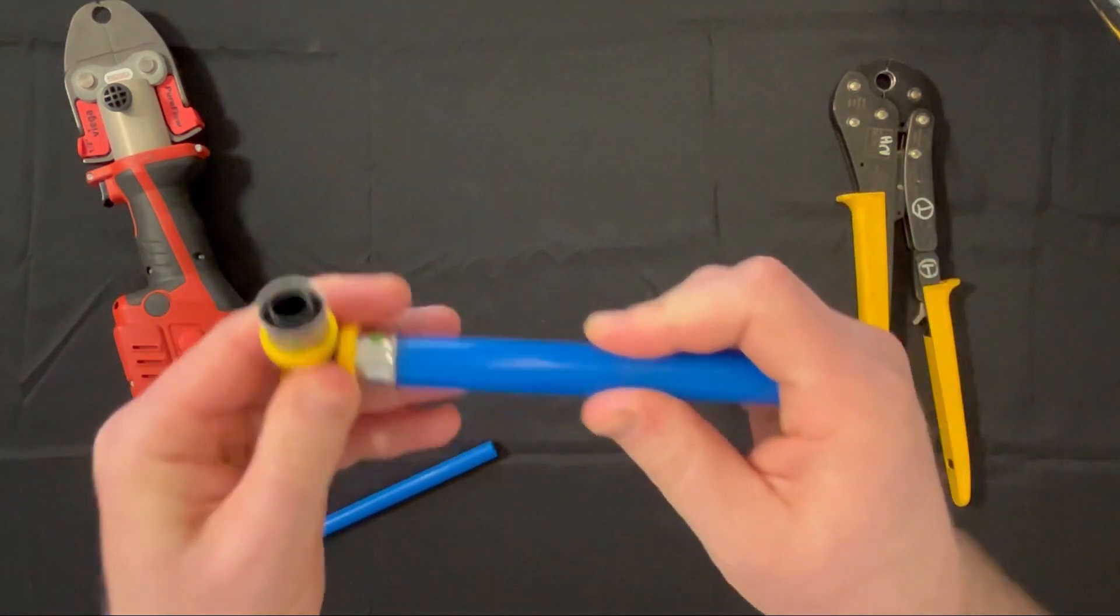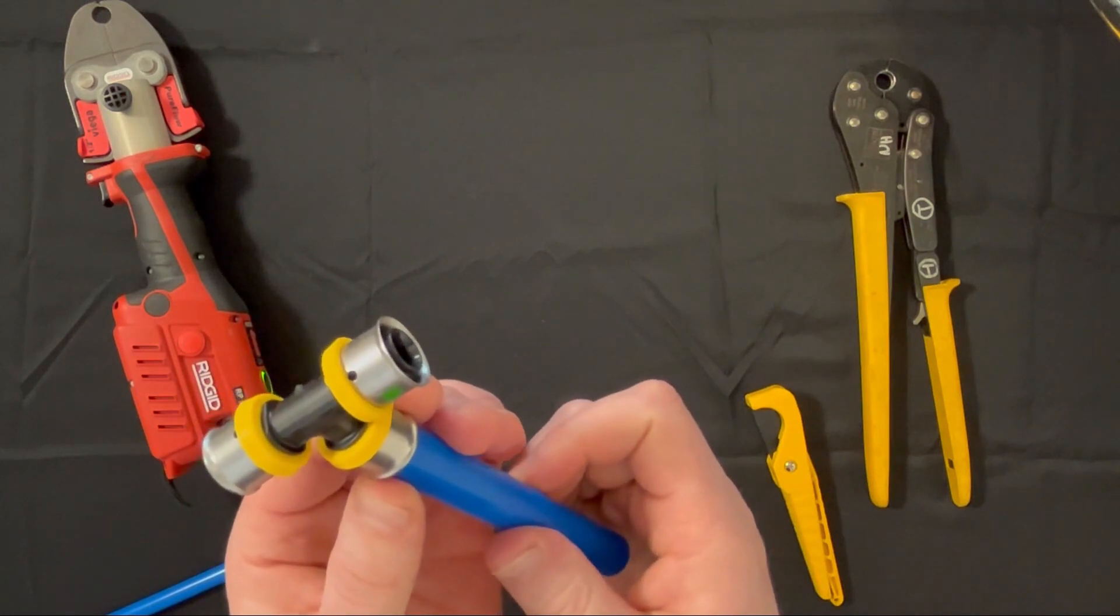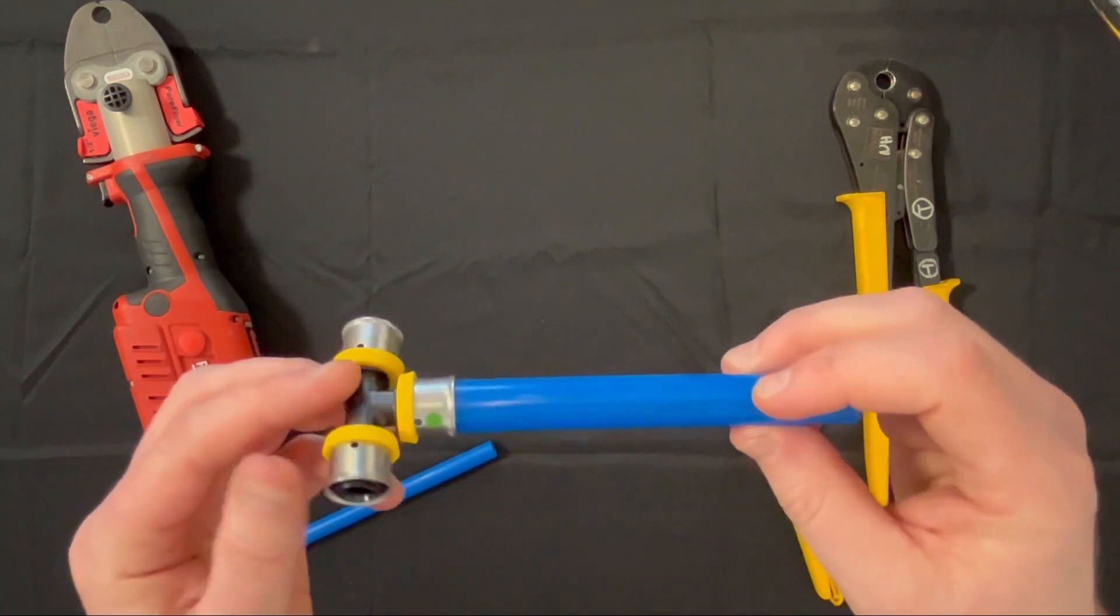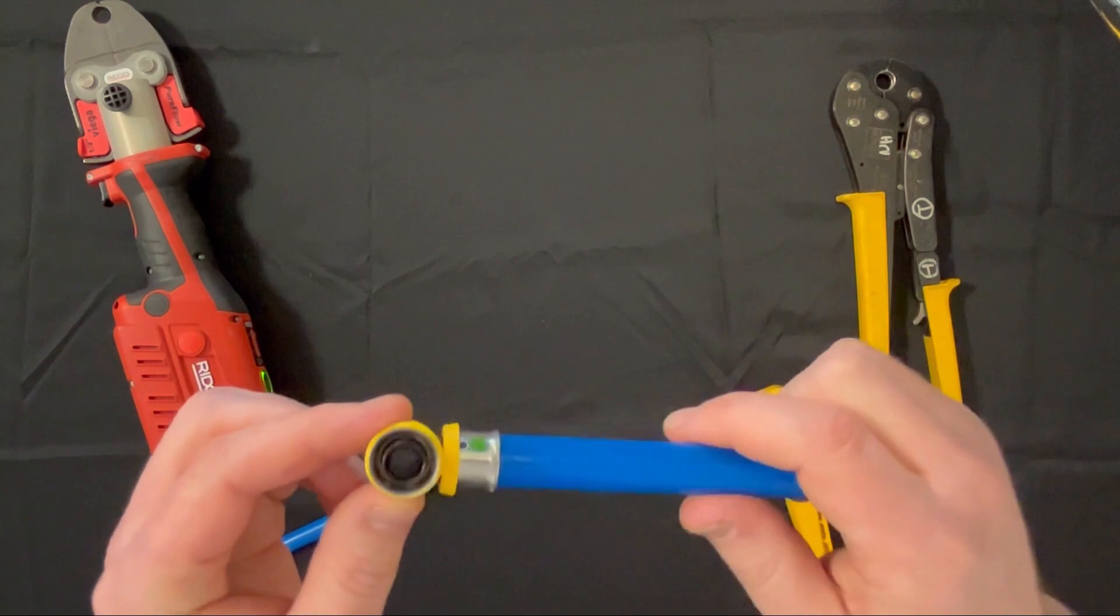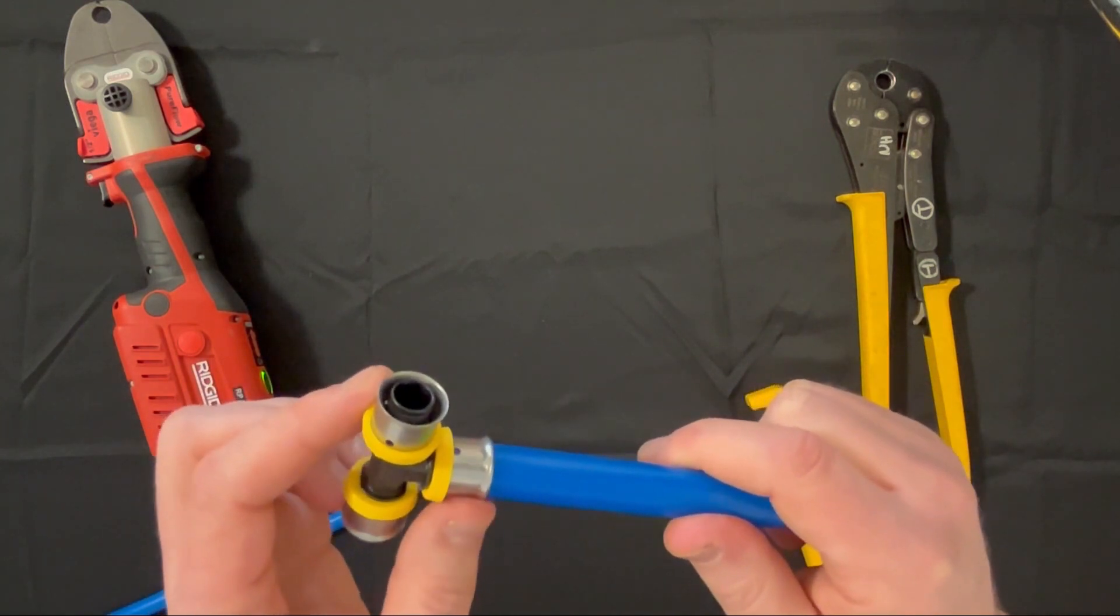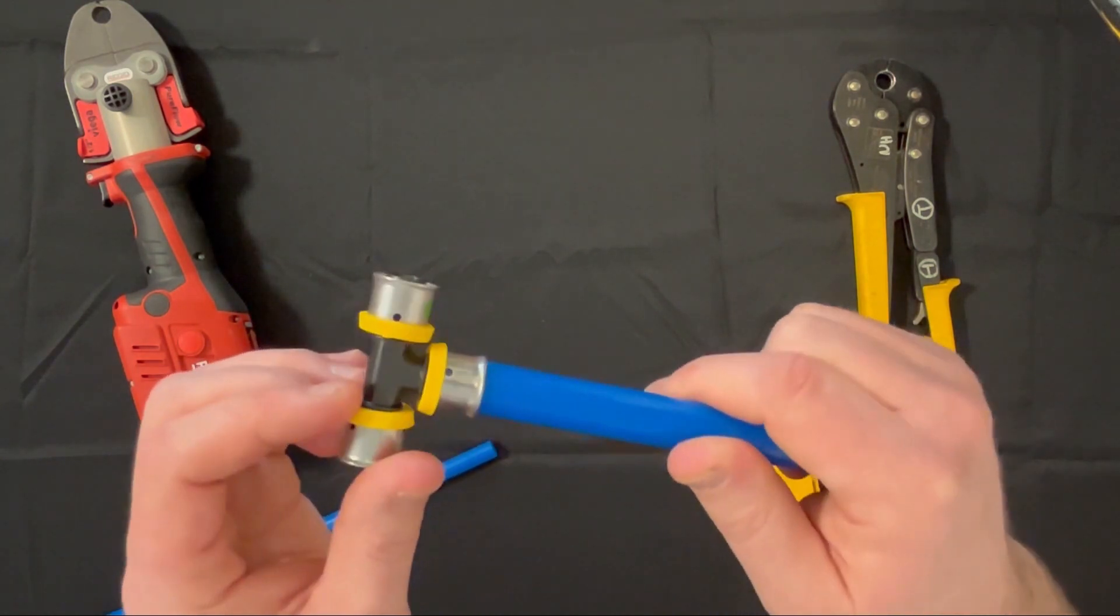We then want to take the fitting and insert the tubing to the fitting and sleeve. With a fully inserted fitting, we will see PEX in two out of the three view holes within the sleeve.